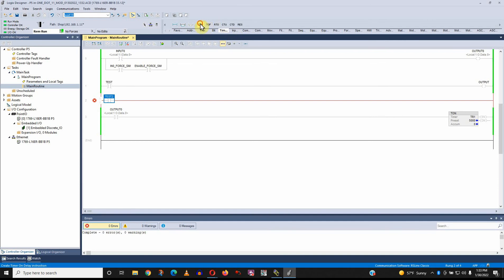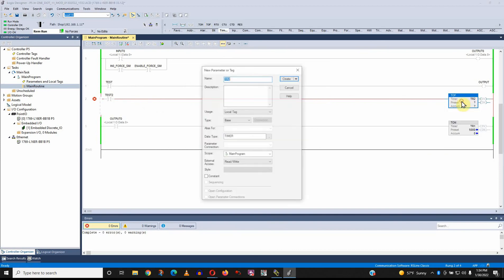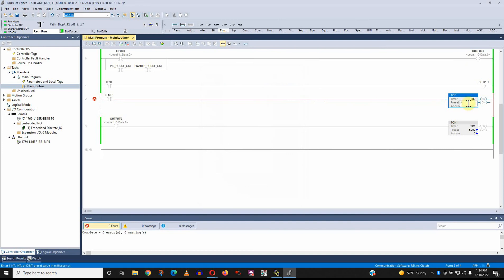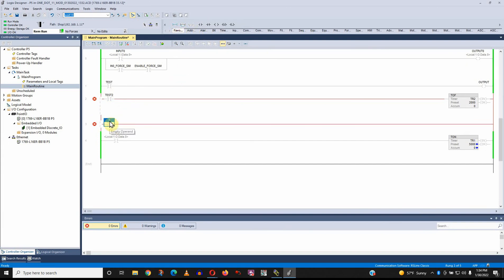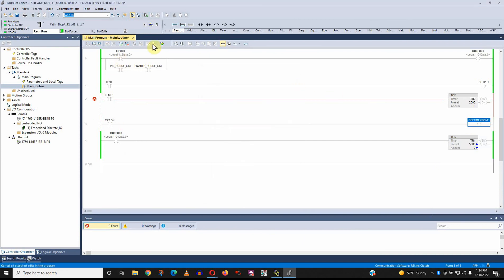Let's go over to a timer. I'll put an off timer. Off timers are interesting. We're going to call it TR2 — I have to right click, new TR2, create that. Let's do a two-second off timer. Let me add another line in here. On this one I'm going to use TR2.done, and I'm going to put a coil out here called off timer done. Let's make a new one of those, and I'm going to accept all changes and finalize the edits.